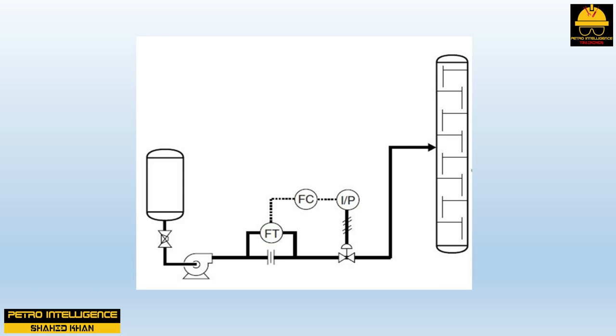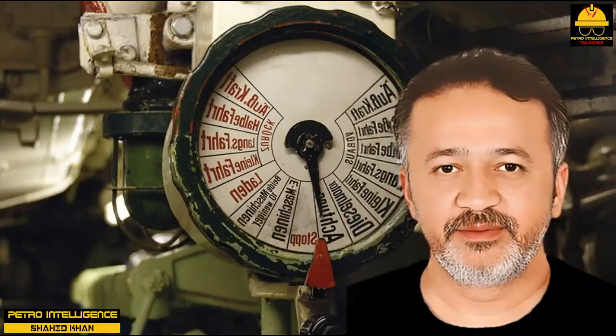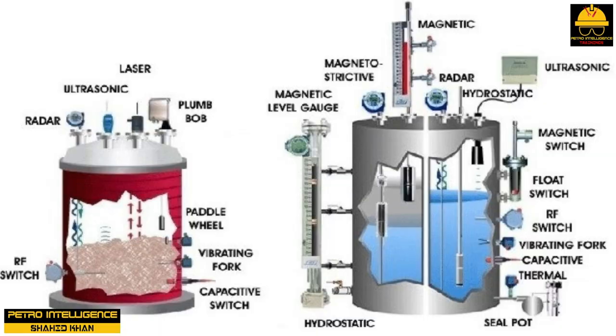Orifice plates create a pressure differential that can be measured by a DP transmitter. Primary elements are typically used in conjunction with a transmitter; although it appears the primary element is interrupting the flow, it is not — increased velocity across the orifice plate compensates for the restriction. The transmitted signal is sent to a controller that compares the incoming signal with the desired set point; if a change is required, the controller sends a signal to a final control element.